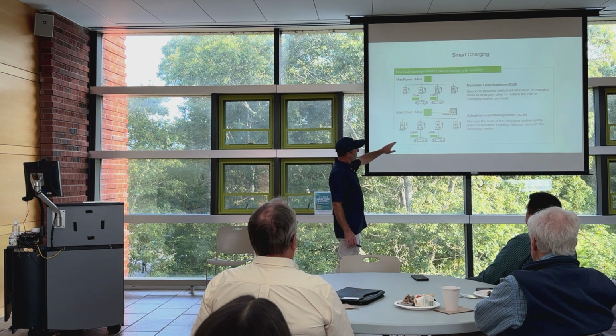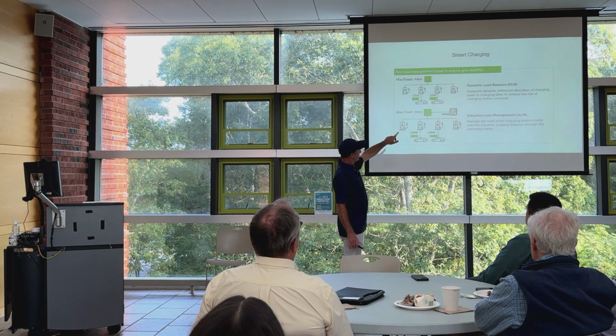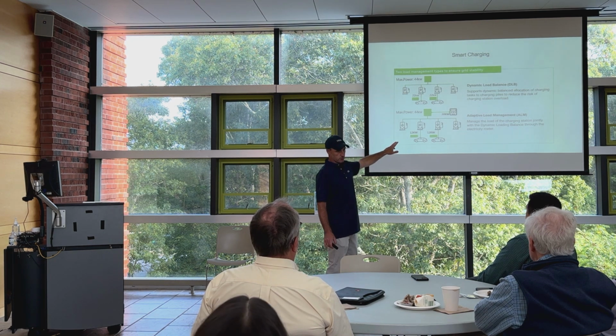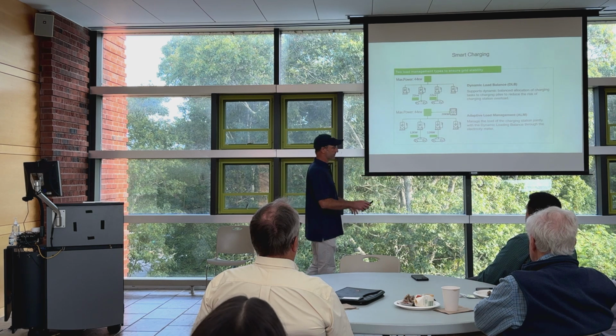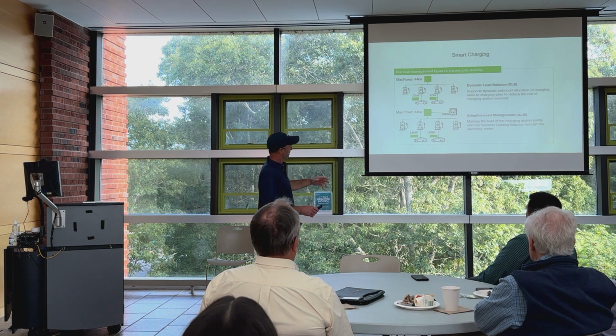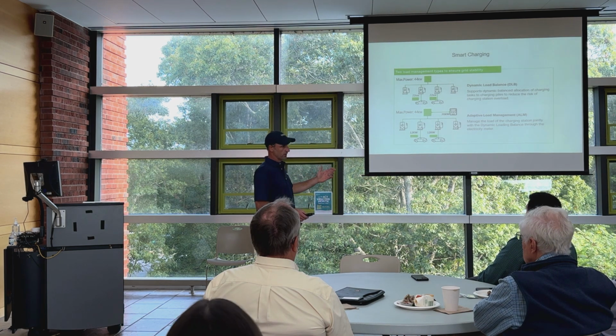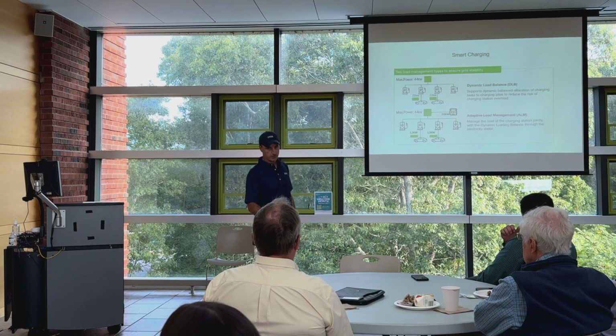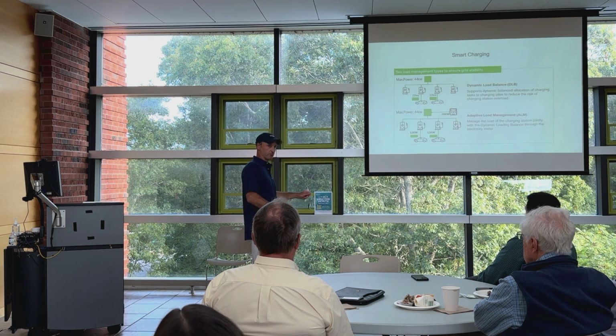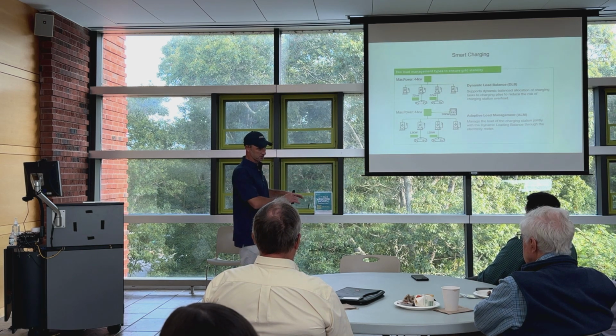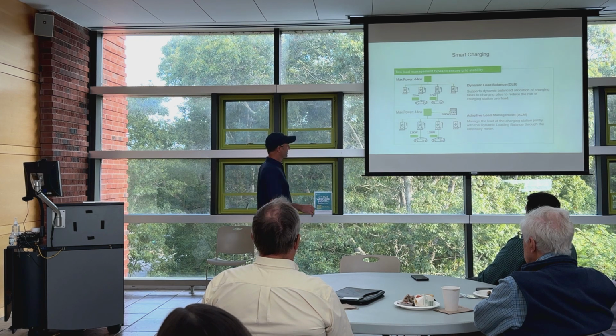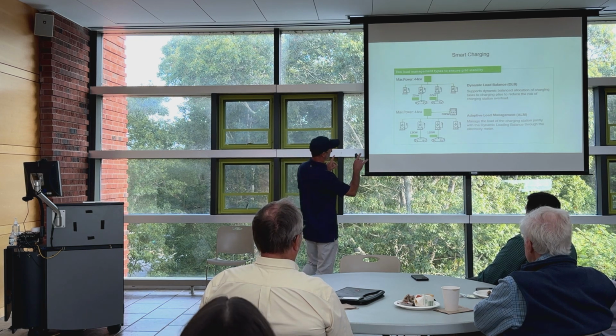The dynamic load balancing allows two automobiles to split that charge, so both are maxed out at half. The software lets us set priority users, so this spot never gets depleted - that's the boss's spot. If the boss parks here, he gets 100%, and the other guy gets whatever's left. Most of the time, it's shared.